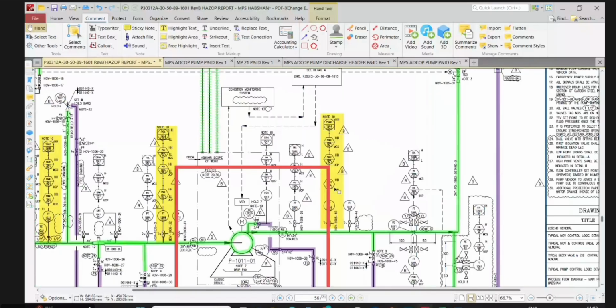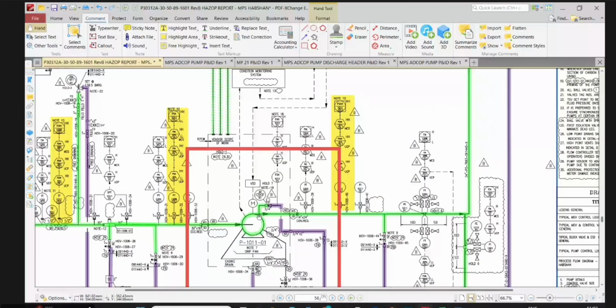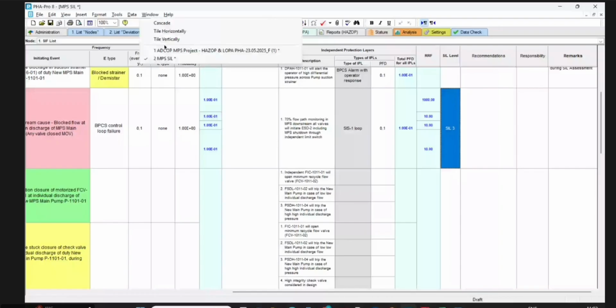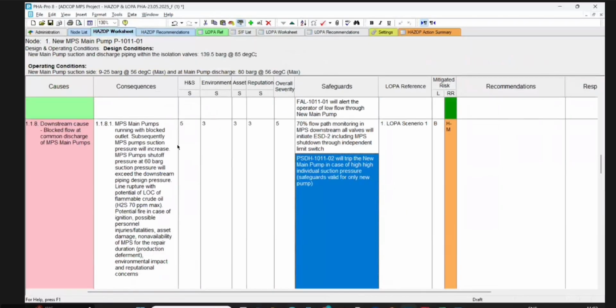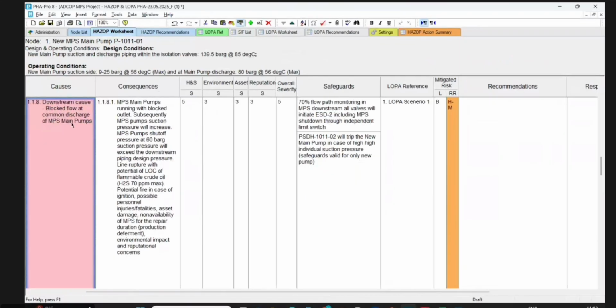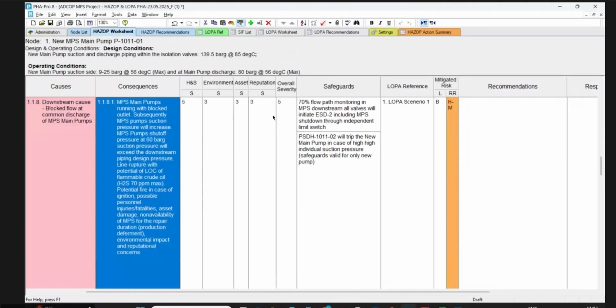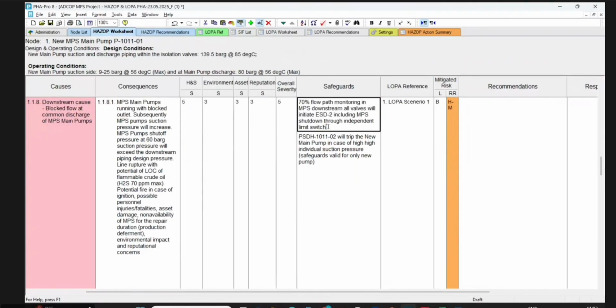Yes, because in the HAZOP, can you show it? Yes, in the HAZOP, I will definitely come back to you. Okay, let me share. If you see the HAZOP, HAZOP has considered only this safeguard in case of downstream blockage. So this is the cause. This may be the IPS blockage or BVS blockage, Dilshad. There was only a recommendation also for a higher pressure trip.